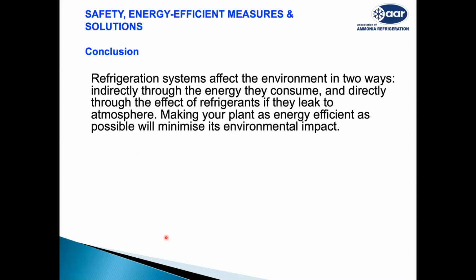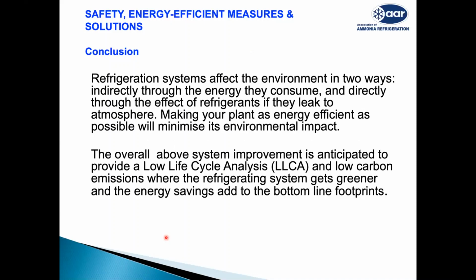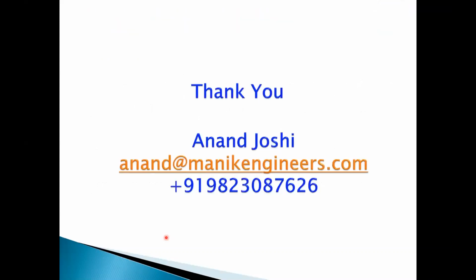And that is how the refrigerant system becomes energy efficient, with no leakages and no damage to the environment. There is a reduction in the carbon footprint because of operating at lower energy and lower discharge pressure, so heat rejection is reduced. There is no wastage of ammonia as a refrigerant and power consumption is reduced. So overall, a low life cycle analysis was generated for the plant. Carbon emission was also reduced. The system becomes more green. As you know, ammonia is a green refrigerant, operating at better conditions with lower discharge and higher suction, which saves a lot of energy.